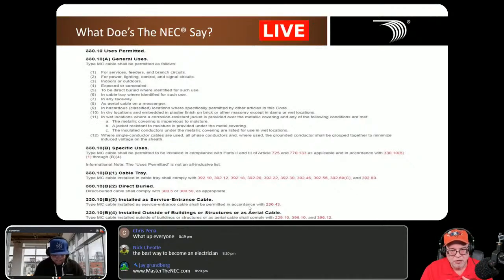So 330.10(B)(3) - can I use MC cable as service entrance cable, Jay? Absolutely you can, in accordance with 230.43. Of course if it's outside it would have to be PVC jacketed, which we'll talk about later, but you most certainly can use MC cable as service entrance cable.